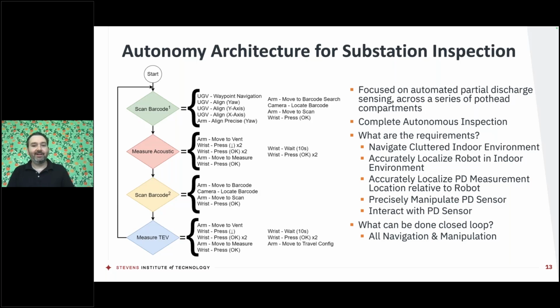To do that, we had a parallel parking procedure where the robot would drive down the aisle of the substation and reach the cabinet that it wishes to inspect. It would turn to face the cabinet, then drive forward and align itself. Once it was properly aligned, it would reach up with its arm and use the depth camera on the tip of the arm to ensure that the arm was properly aligned with the panel to begin making physical contact. The joints of the arm also had their own onboard torque sensors that allowed us to determine that physical contact had been made.